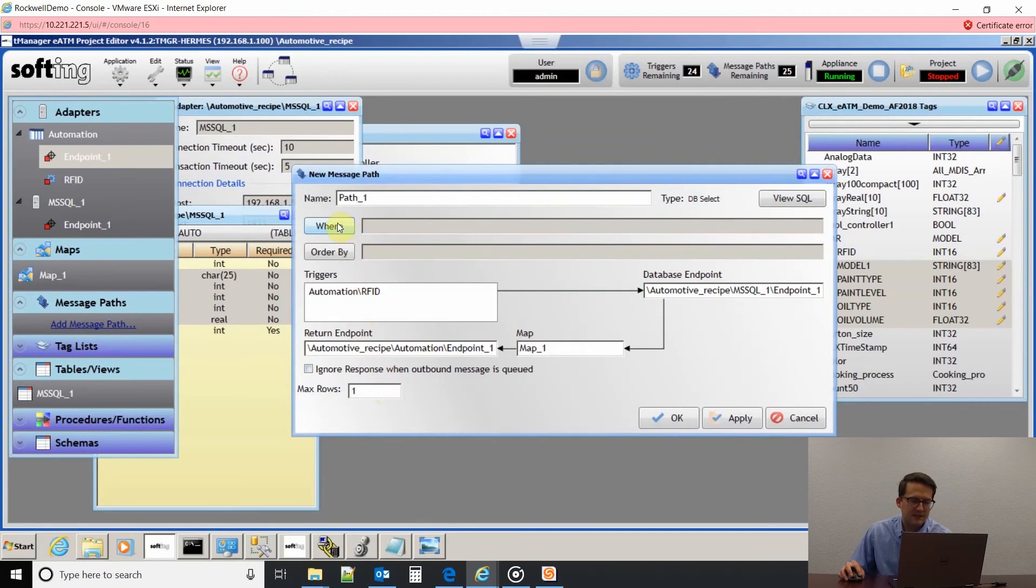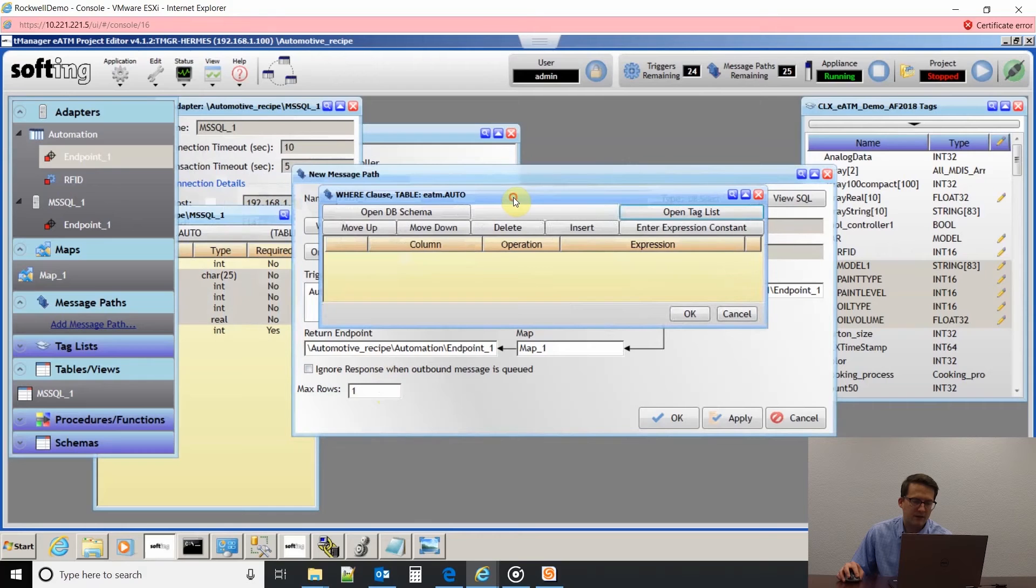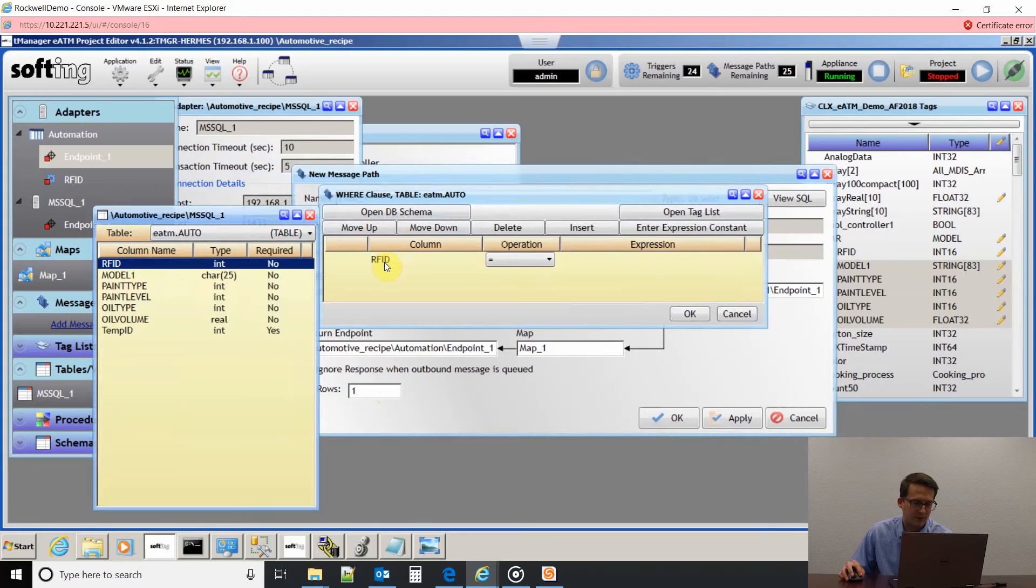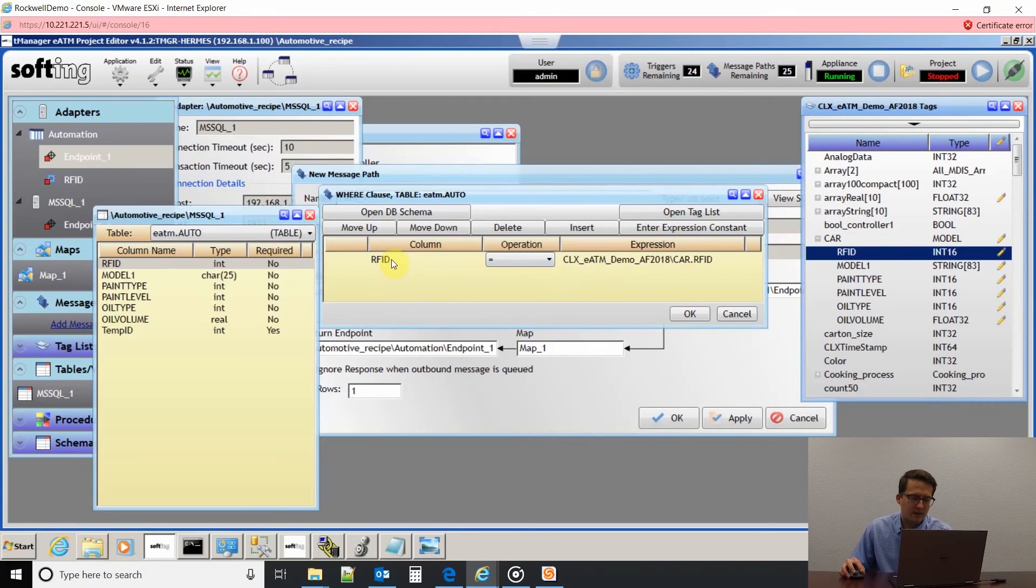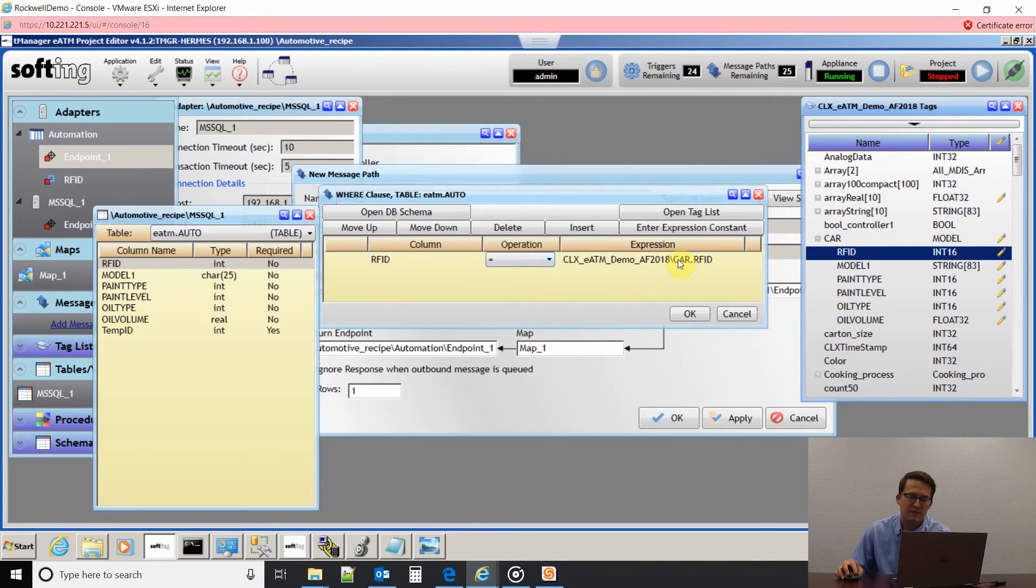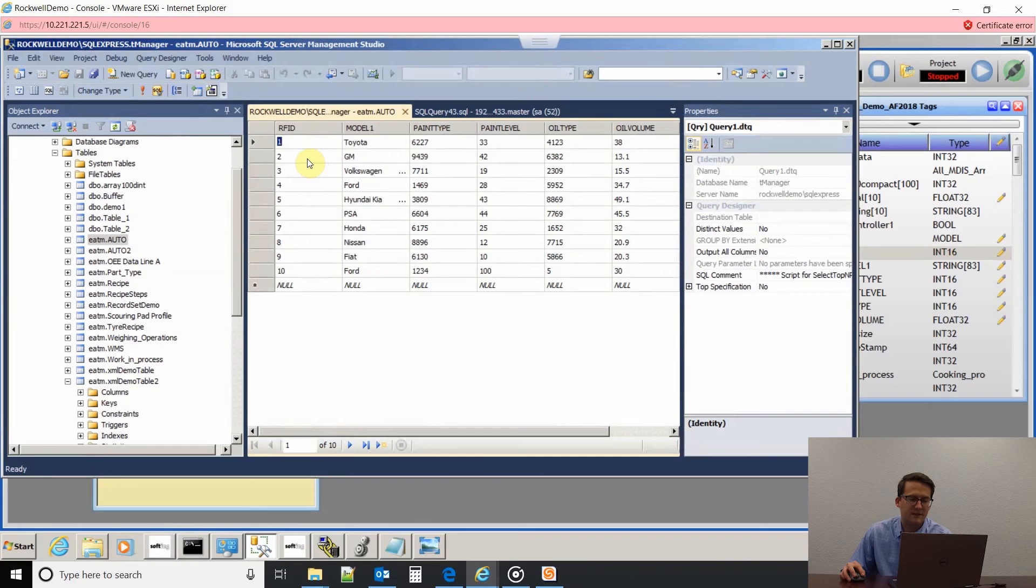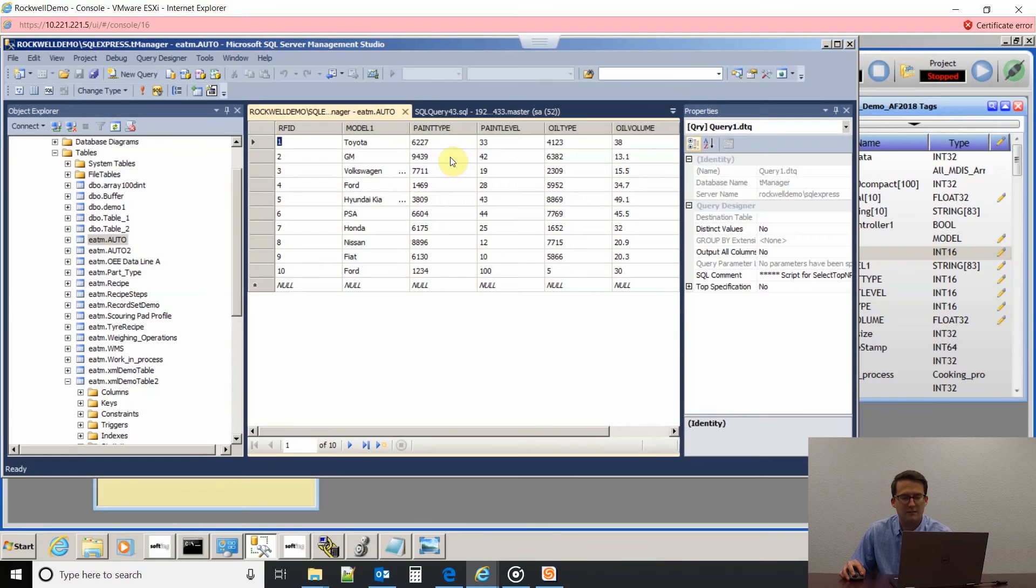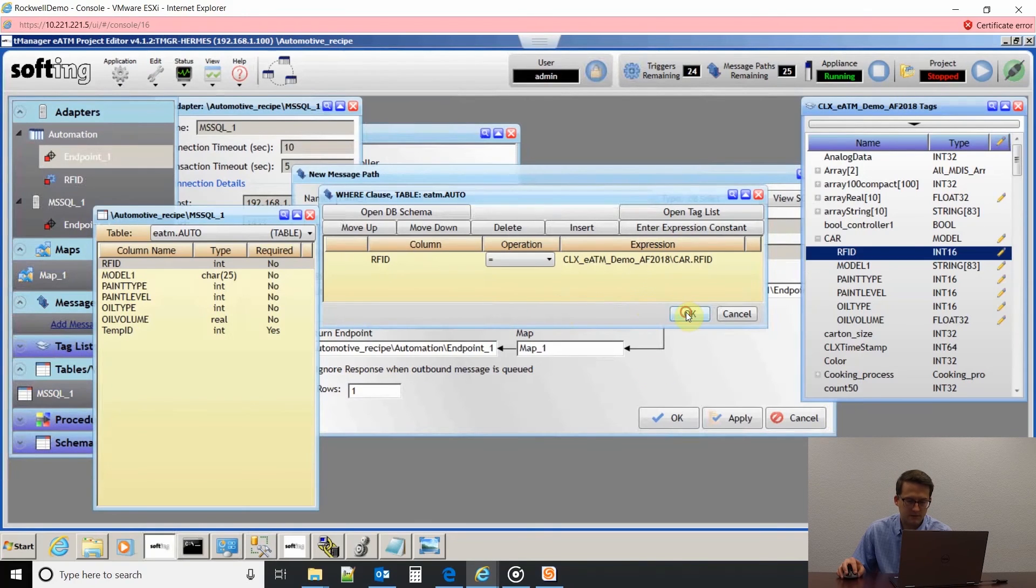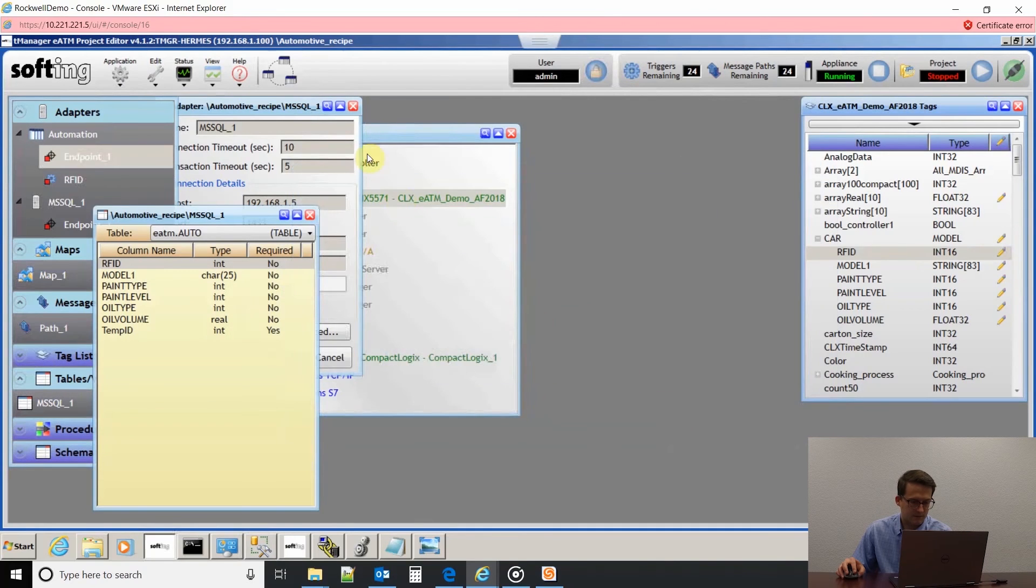We also need to set up our where clause. Our where clause is telling T-Manager where we're pulling data from. I'm going to open up database schema, click and drag and drop the RFID tag. Then I'm going to open up the tag list and drag and drop it in there. What this is saying is we're going to pull data in the database where the RFID matches the RFID tag in the PLC. If I have a 2 in my PLC, it's going to come into the database, look at this table and say, oh, here's where RFID equals 2, pull this model, this paint type, paint level, etc. into the PLC.